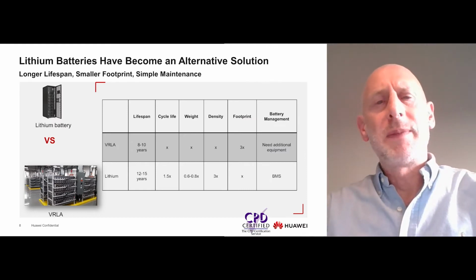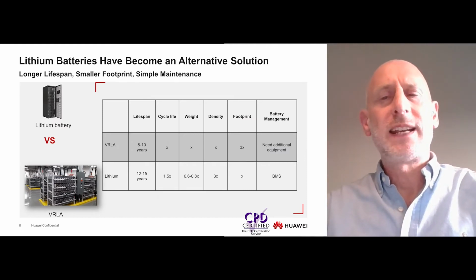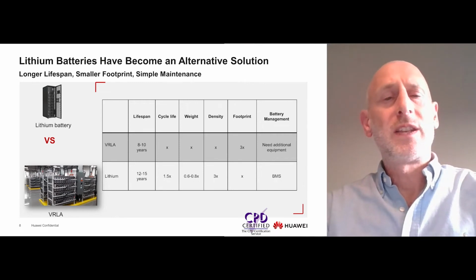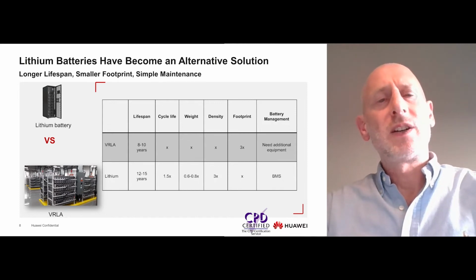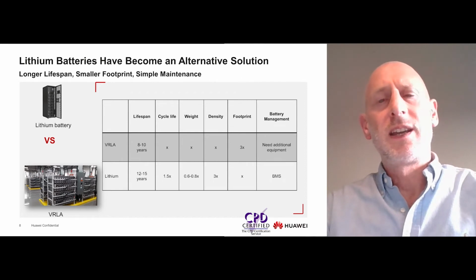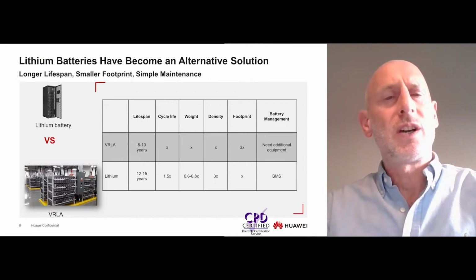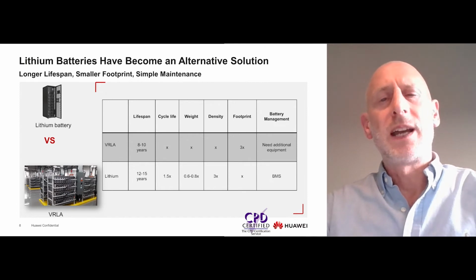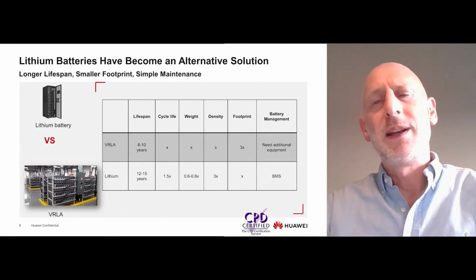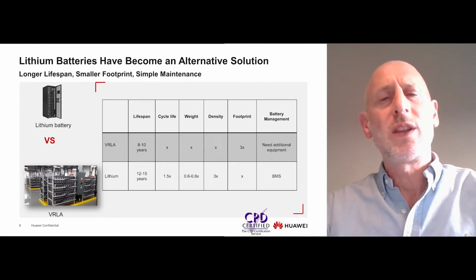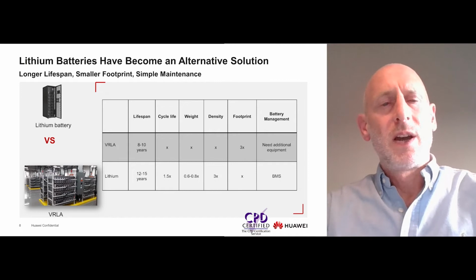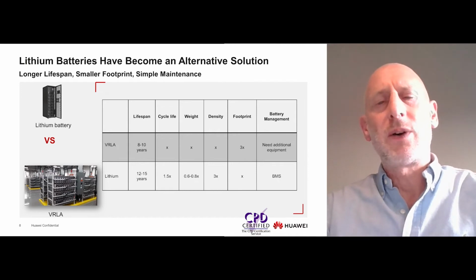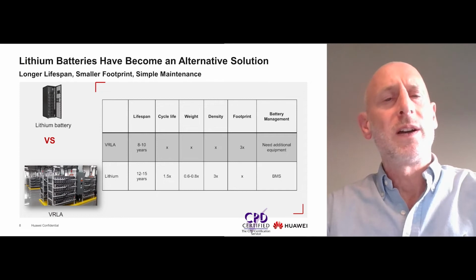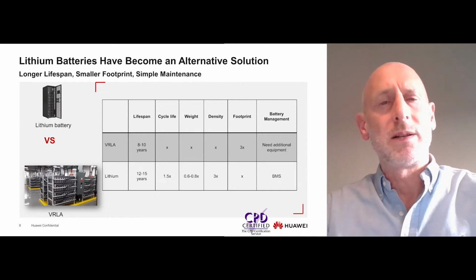There is still debate among many organizations favoring more traditional lead-acid battery solutions as the best option for data centers. Huawei believes that the benefits of lithium-ion batteries make them much better suited to the growing market. Lithium-ion technology tends to have a much higher energy density, can achieve an 85% depth of discharge compared to lead-acid's 50%, and is usually 95% or more efficient, meaning almost all of the larger amounts of energy stored in the battery can be harnessed. For a data center, the higher availability of power means the supply is readily available for longer and can keep up during periods of increased demand.